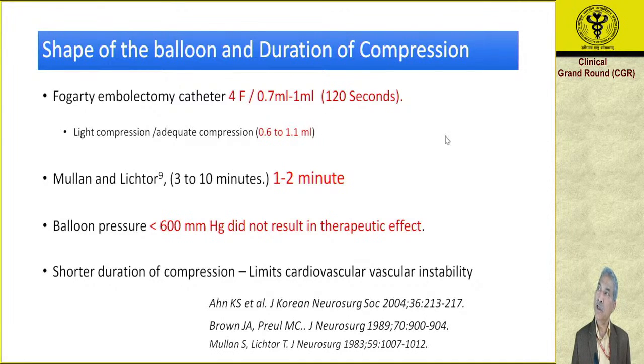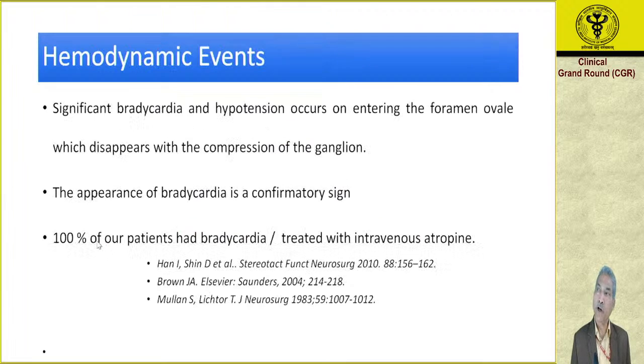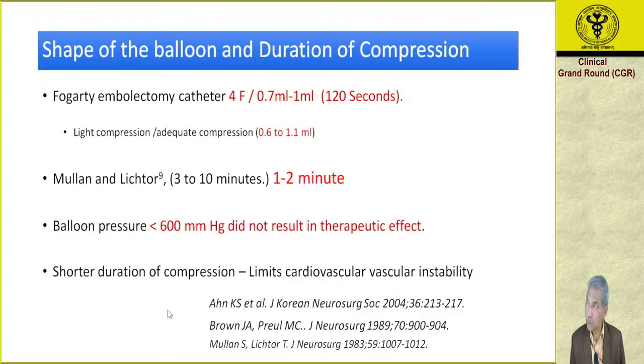In clinical literature, initially, in the very first study, they inflated the balloon for 3 to 10 minutes, but later on most of the investigators use 1 to 2 minutes. We also follow the same dictum. In studies where they monitored the balloon pressure, they found that if the pressure achieved is less than 600 millimeters of mercury, the therapeutic effect is not so much. For effective pain relief, the pressure should be more than 1.3 atmospheres, that is around 1000 millimeters of mercury, and usually the pressure achieved is between 1.3 and 1.7 atmospheres.